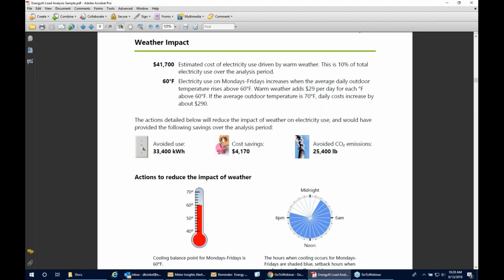So we do the standard regression. I mentioned at the outset that this is not a true M&V analysis in the sense that we don't adhere to some of the same thresholds. One of the most obvious ones is weather, where typically you want a correlation coefficient of 0.75 or higher to really establish a firm correlation with weather. We actually go with a lower one. We go with 60%, because what we want to do is take our best guess as to whether the facility is affected, whether energy use is driven by weather.